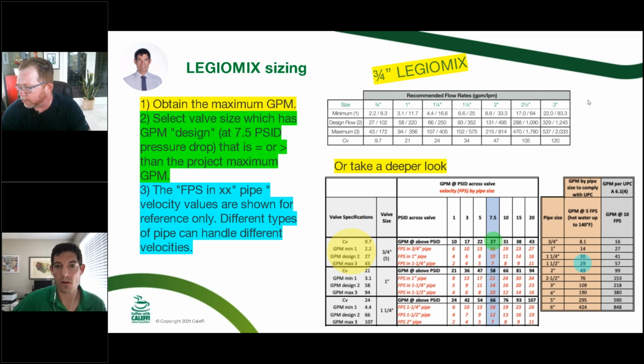A few comments from people who did the math in the background. That's how you can always tell when you've got smart people participating. And they've rightly pointed out that at 30 gallons per minute, thank you, Patrick, be careful what pipe size you're using because your flow velocities are going to be very high. And like you pointed out, that 5 feet per second, outside of that, the Copper Development handbook isn't going to like that for copper. And then for PEX as well, you're going to go slower through that.